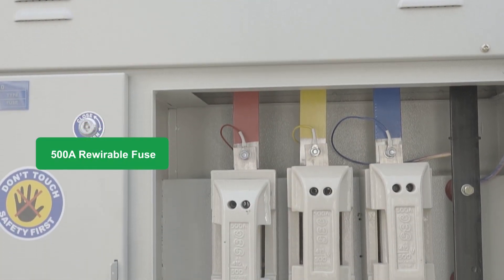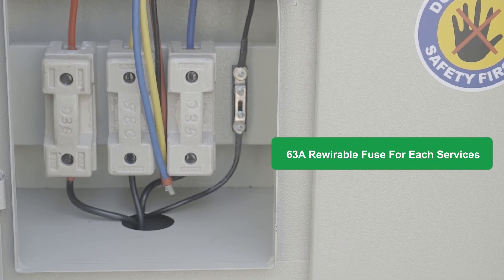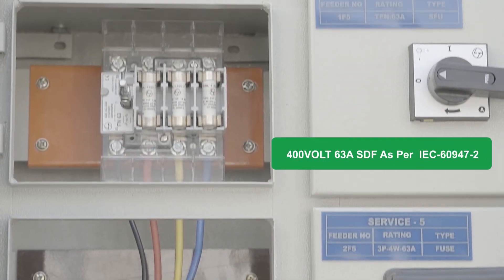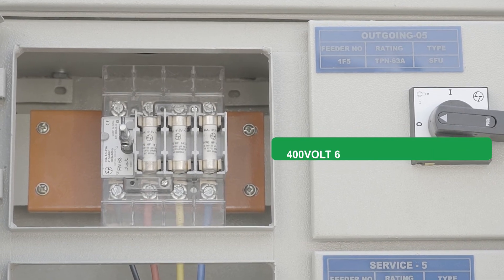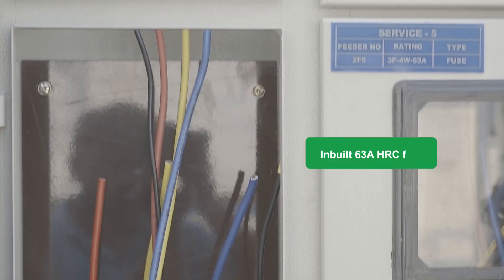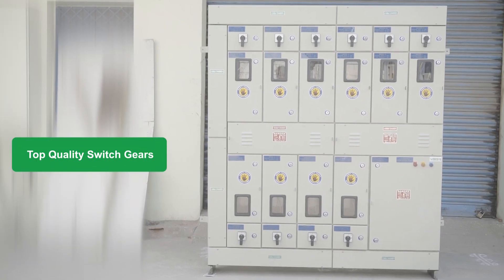We have used 500A re-wireable fuses for the grid incomer cable and 63A re-wireable fuses for each service. Each three-phase service output is connected with a 400V 4-pole 63A SDF as per IEC 60947-2. SDF means switch-disconnector fuse, which has a built-in 63A HRC fuse. We use only top-branded switchgears.